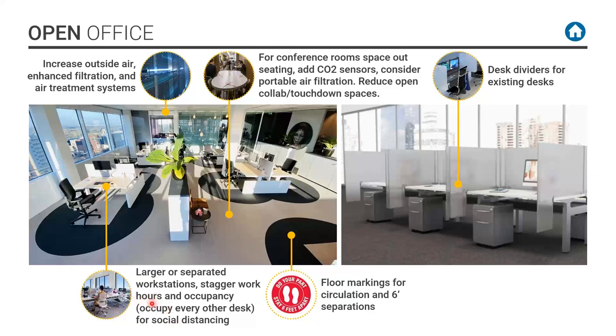So now we've gone up to our office floor, and what are the things we might want to consider? Of course, larger separated workstations, staggering hours, increasing the air, again, better air quality in the space. For conference rooms, spacing out seating. I mentioned perhaps adding CO2 sensors, and consider portable air filtration. We're considering that for a couple of reasons. Smaller rooms don't necessarily have the air circulation. And if you get an air cleaner, a HEPA type filter that's sized at a minimum of 4 air changes per hour, it can do a good job in removing what's in the air. Also psychologically, it makes people feel better.